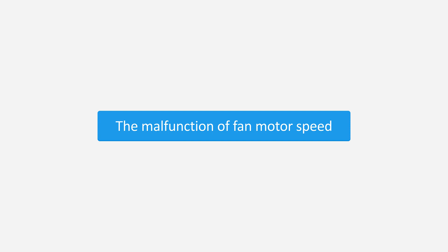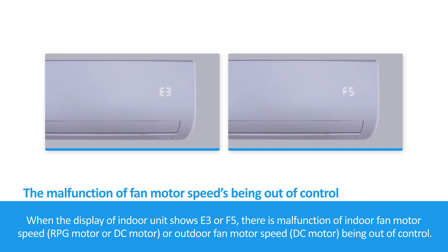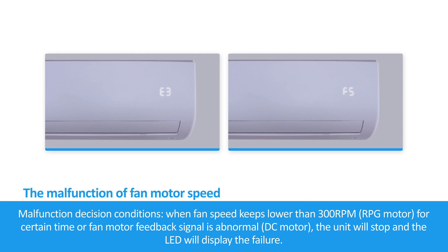The malfunction of fan motor speed. When the display of the indoor unit shows E3 or F5, there is a malfunction of indoor fan motor speed — RPG motor or DC motor — or outdoor fan motor speed, with DC motor being out of control. Malfunction decision conditions: when fan speed keeps lower than 300 RPM for a certain time, or the fan motor feedback signal is abnormal, the unit will stop and the LED will display the failure.